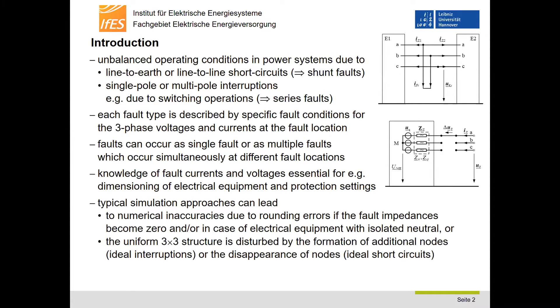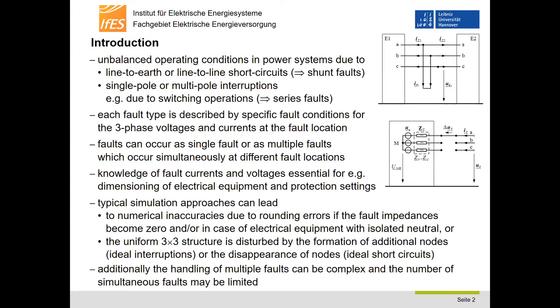The necessary calculations of fault currents and voltages using typical simulation approaches can lead either to numerical inaccuracies due to rounding errors if the fault impedances become zero, as well as in case of electrical equipment with isolated neutral, or the uniform three-by-three structure is disturbed by the formation of additional nodes when having ideal interruptions, or the disappearance of nodes when having ideal short circuits. Additionally, the handling of multiple faults can be complex and the number of simultaneous faults may be limited.